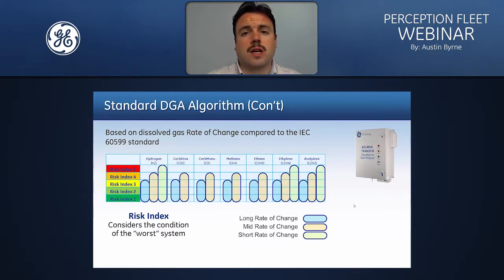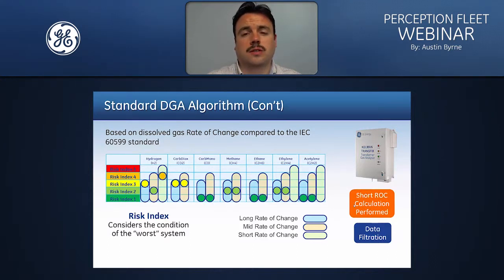Again, as the online monitor takes a sample from the main tank, it looks at the long rate of change and performs the long rate of change calculation within the perception algorithm. Again, the data is then filtered to ensure that we don't have any spurious information, and the measurements are then taken and applied within the algorithm. We perform the same calculation for the mid rate of change and then also for the short rate of change to establish which rate of change is considered to be the worst for that asset. So you can see that acetylene has pushed this particular asset into a risk index of 5. So you can see 5 is the categorization that it's given.